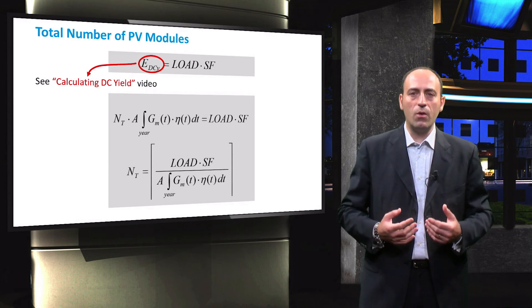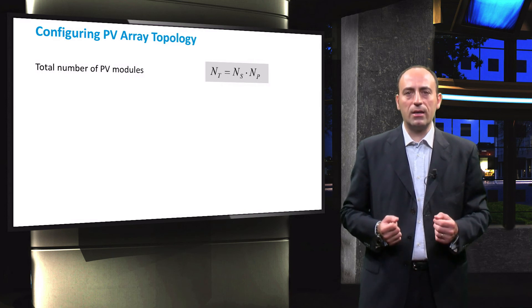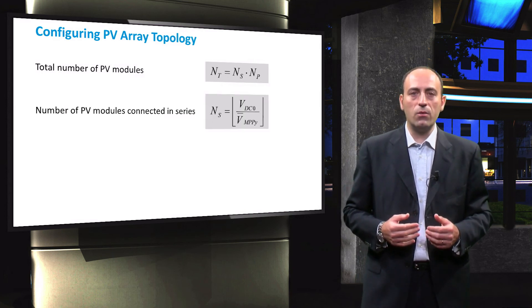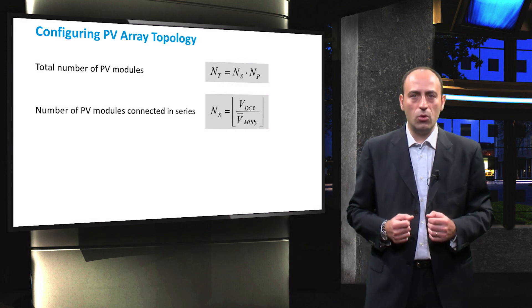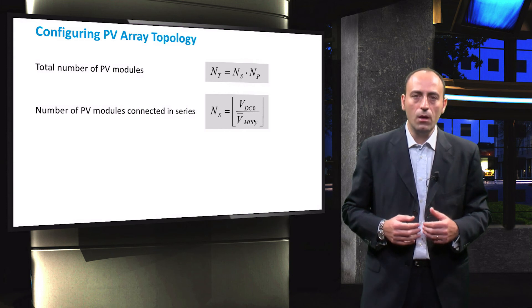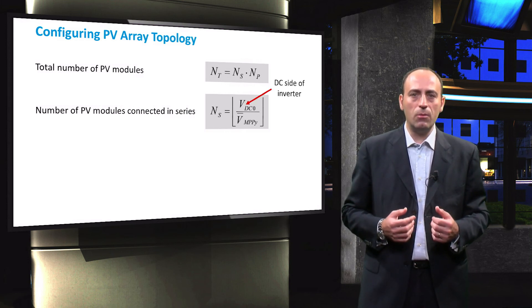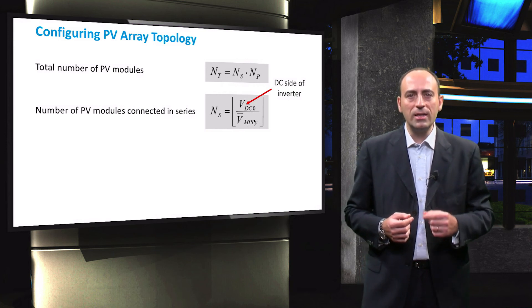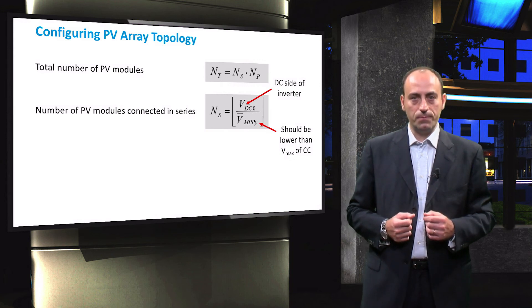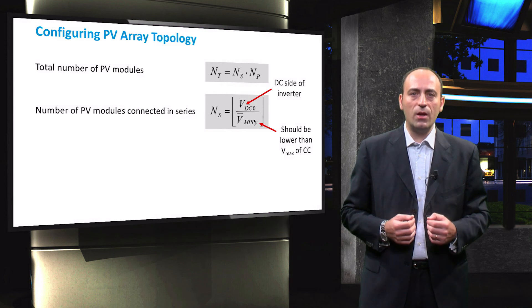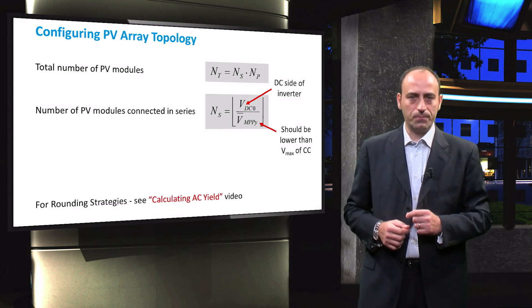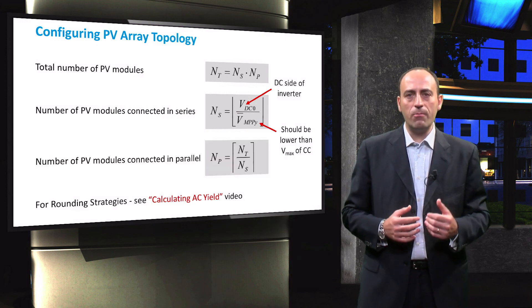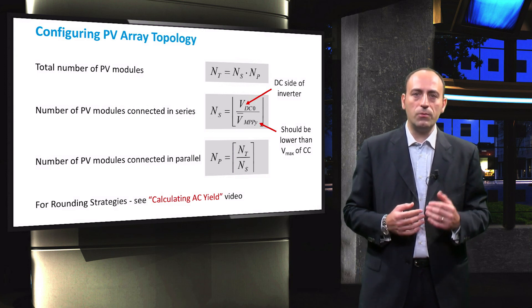Once the total number of PV modules required is determined, the number of modules in series and in parallel are calculated. The number of series-connected modules is calculated by dividing the nominal DC voltage of the inverter by the averaged maximum power point voltage of the PV module, as explained in the 'Calculating the DC Yield' video. You have to keep in mind that this averaged maximum power point voltage of the PV module should be smaller than the maximum voltage of the charge controller to avoid damage to the latter. The resulting value is rounded down to its nearest integer. Finally, the number of PV modules in parallel is determined by dividing the total number of PV modules by the number of PV modules in series, with the resulting value rounded up to the nearest integer.